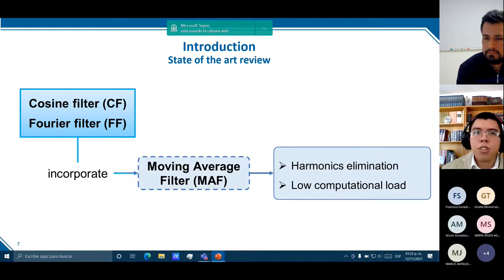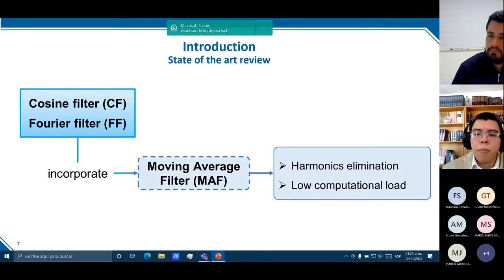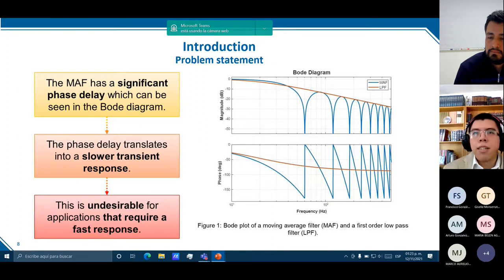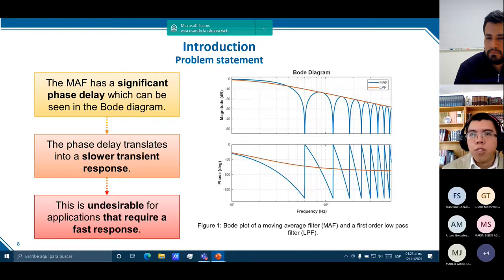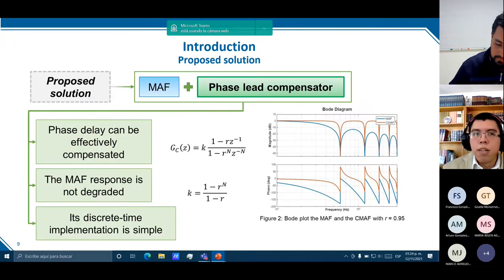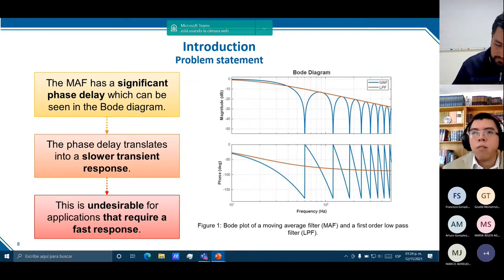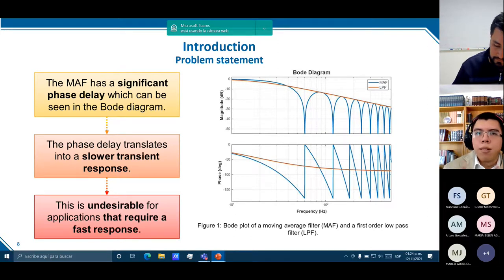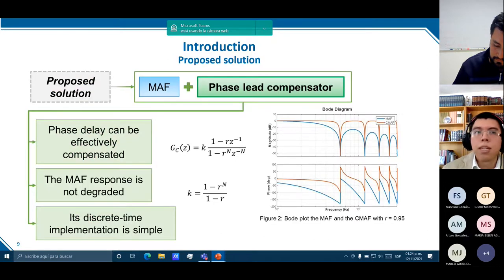The DFT-based techniques are the cosine filter and the Fourier filter, both incorporating a moving average filter — MAF — which stands out for its low computational burden and harmonics elimination. Nevertheless, the problem with the MAF is that it causes a significant phase delay, which becomes evident under step changes as deduced from its Bode diagram depicted in Figure 1. This delay translates into a slow transient response, which is undesirable in applications requiring fast response, like protection systems. Solving the MAF's phase delay problem would contribute to a phasor estimation algorithm capable of dealing with harmonics, with low computational load, and faster transient response.